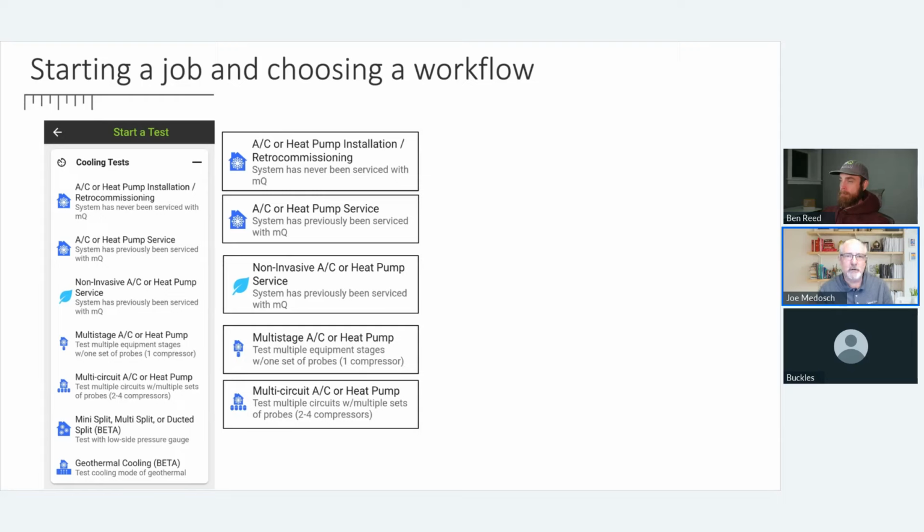It's a whole new world where we don't really know what their vapor line or suction line or other pressures or temperatures should be, and they don't either. So we are trying to resolve this as a process for third-party verification. But currently, you can use it, but we've moved it to a beta because there can be challenges on what your results may be.